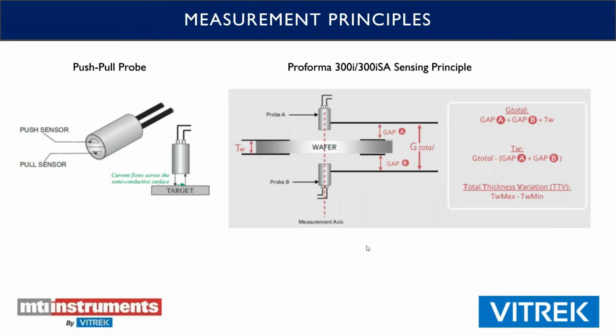We use one on the top of the machine, or on the top of the wafer, and one on the bottom. And you can see the math on the right is how we calculate both the thickness and the shape of the wafer as it moves between the two probes. So you can get thickness variation. There's a host of different measurements that you can do, but this is the technology used for that.